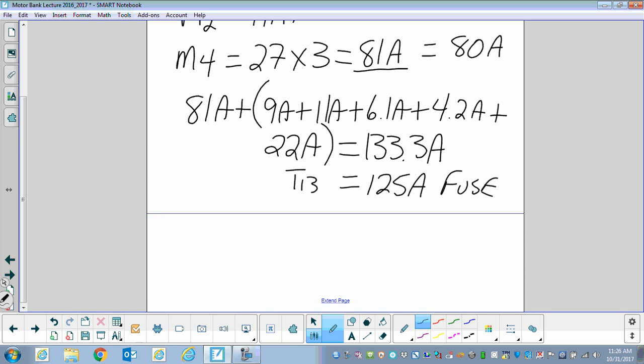When there's a mix of breaker types, you do have to change them all and treat them accordingly. When we were looking at wound rotor motors, that has a different multiplying constant, so you have to be careful. You can't just go by the largest FLA — you have to go through the full process for each motor type.